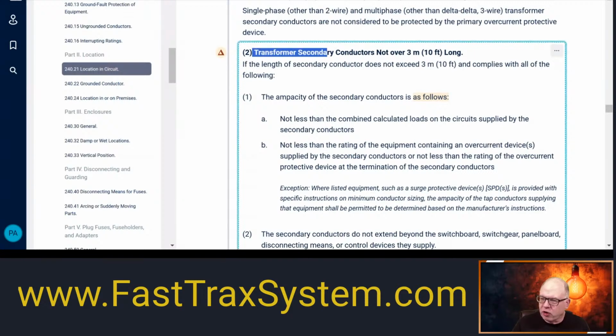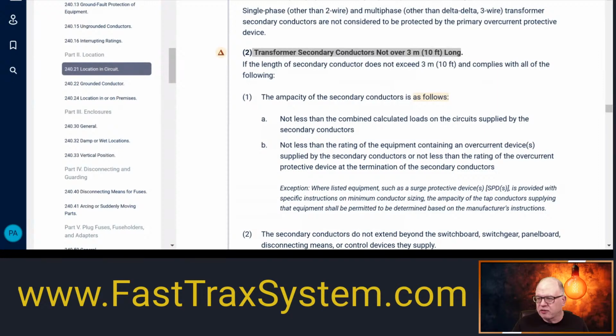So, all right, here's the first. We're talking about transformer secondary conductors not over 10 feet. Okay, so the concept of this, if I had to paint a mental picture: you folks are familiar with it, you've got your panel, you have a breaker, you're coming out, you're feeding a transformer, a dry type transformer, right? Out of that transformer, we're coming out with what's called secondary conductors. They go straight to the lugs on the secondary, and they'll typically go over to a panel enclosure and terminate into typically a main breaker, right? And so those conductors are considered secondary conductors.